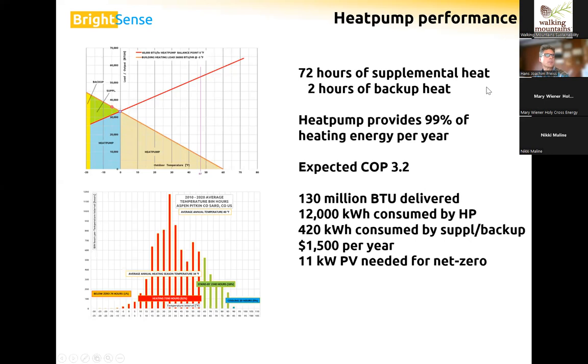We would need about 2 hours of 100% backup heat. So this yellow in a typical year, 2 hours, that's nothing. And those bitter cold hours, they typically happen early in the morning, just before the sun comes up. And so if you have a well-insulated home, you would be coasting right through those 2 hours, and you wouldn't even notice it.